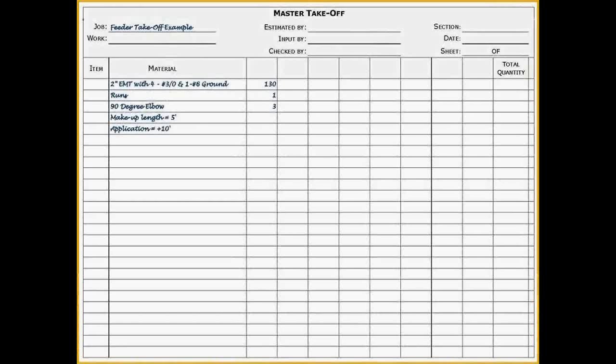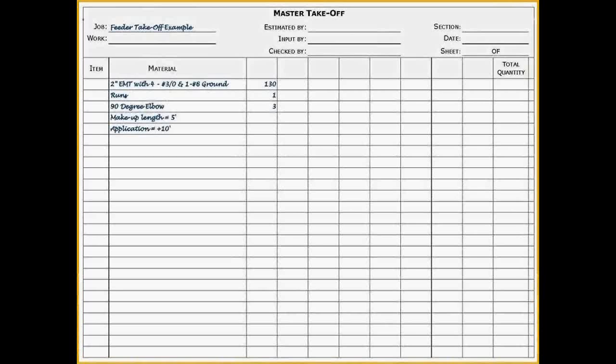In our example, the conduit running into the top of panel MSB I estimate requires seven feet of makeup length. In other words, I calculate it takes seven feet of additional wire to extend past the end of the conduit to the circuit breaker where they must terminate. The wire makeup length needed for the 225 amp panel I estimate would be around three feet. Now seven feet at one end and three at the other makes a total of ten feet. And I divide that or I split it up between the both ends. It ends up being five feet average. Now I'll show you how this is entered in Red Rhino in a moment.